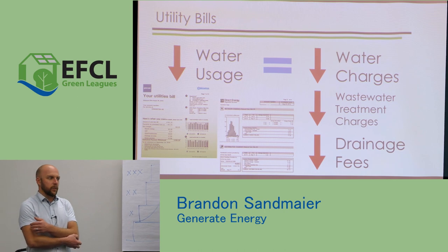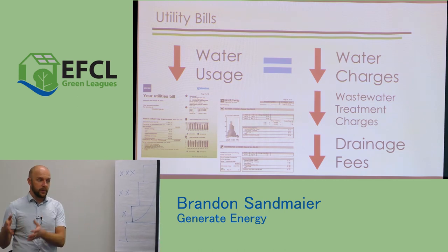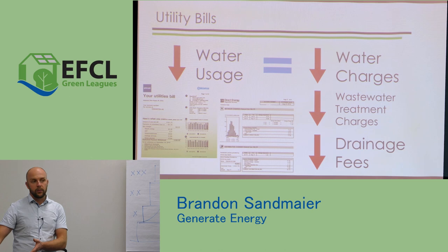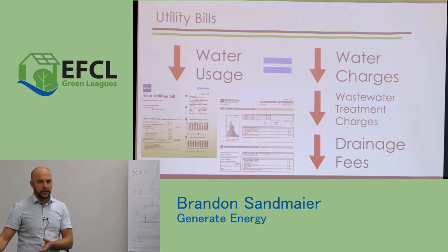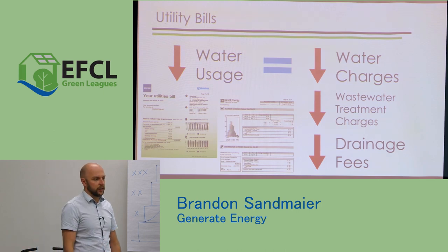Right, so this is where we just do a bill analysis, and we can say, listen, this is what you should do. You should get another meter installed that's just for your ice rink, so that it's only used during the winter time. You might pay a little more. We would find that even though they would pay more to have another meter there, they'd still save like $600 a year. So yeah, it was substantial.